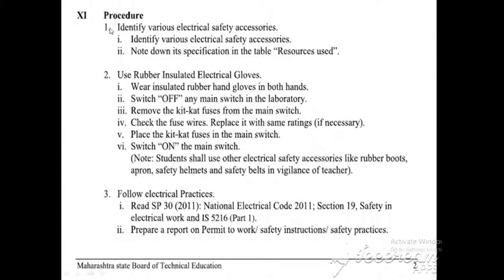Procedure: first, identify various electrical safety accessories and note down their specifications in the resources-used table for whichever safety accessories we use in the laboratory or while working in an electrical place. Then note down the resources used in our specification table. Use rubber insulated electrical gloves — wear insulated rubber hand gloves on both hands. Switch off any main switch in the laboratory. Remove the Kitkat fuses from the main switch. Check the fuse wire, and replace it with the same rating if necessary. Place the Kitkat fuses back in the main switch. Switch on the main switch. Students shall also use other safety accessories like rubber boots, apron, safety helmets, and safety belts under the vigilance of the teacher.